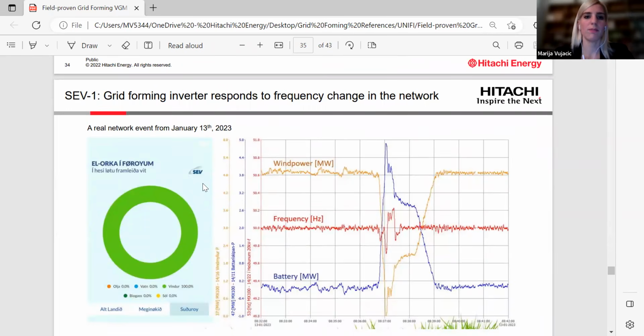This is a real network event which happened on January 13, 2023. You can see how the wind power actually dropped from around 5 megawatt. At this moment, it was only the wind power plant which was in operation, and the power dropped from around 5 megawatt to 0, and you can see here an inherent and immediate response from the battery energy storage system, and how the battery energy grid forming maintained frequency and provided stable operation in quite short time. And within 2 minutes from this network event, the wind power was back to the nominal or rated value.